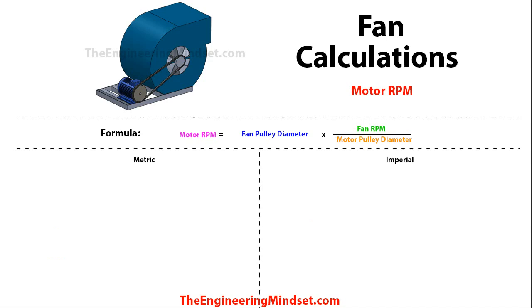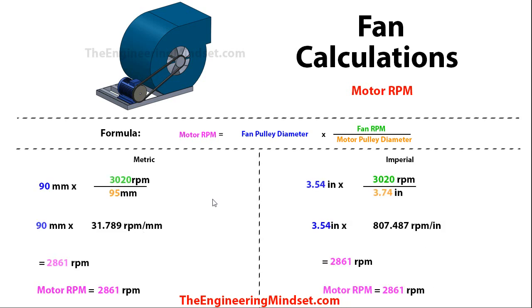We can also calculate the motor RPM using this formula: motor RPM = (fan pulley diameter × fan RPM) ÷ motor pulley diameter. Dropping in the numbers gives 2861 RPM on both metric and imperial sides. You can calculate these or look them up from the manufacturers.